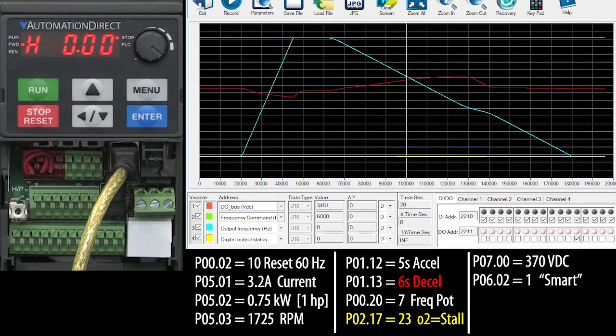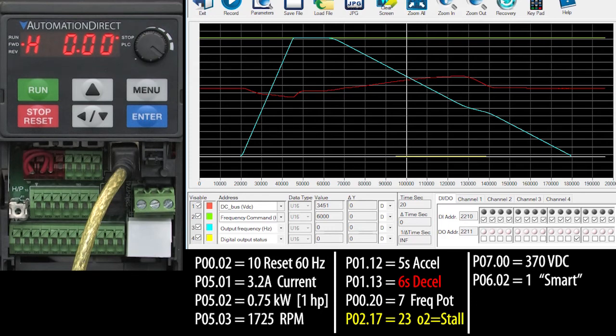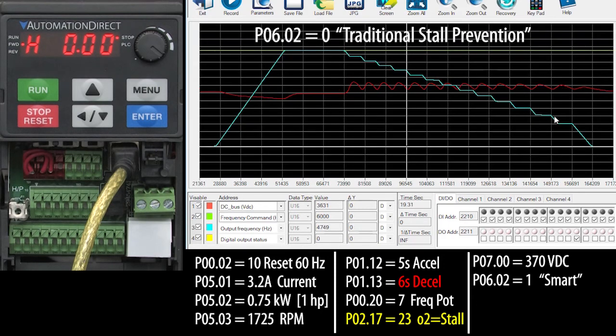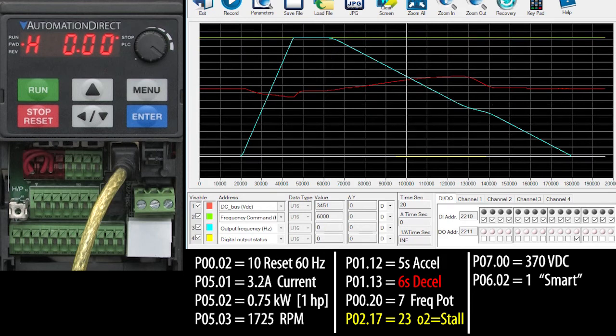You can see the stall prevention is engaged in here and it drives manipulating the deceleration to accommodate the changes in the DC bus voltage. So the traditional method decelerated in about 18 seconds and this method decelerated in about 21 seconds, but that was for this system. Your system might be different, so try both.